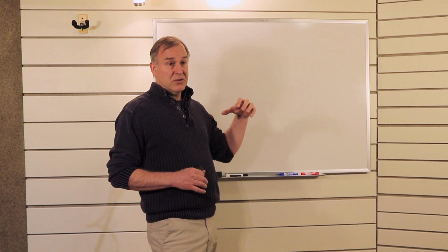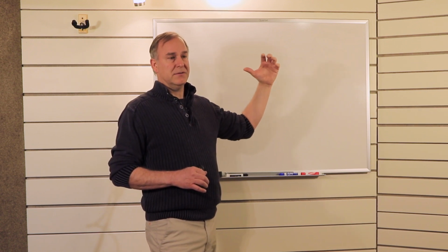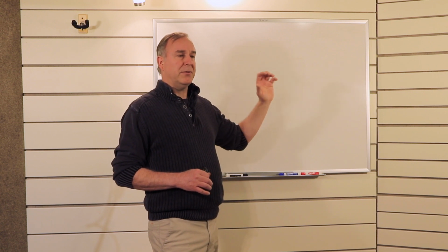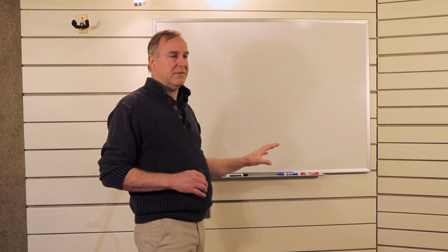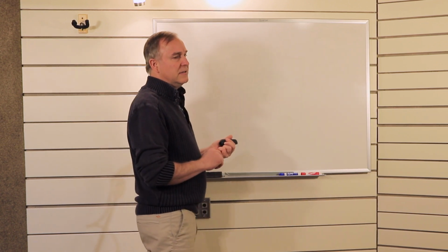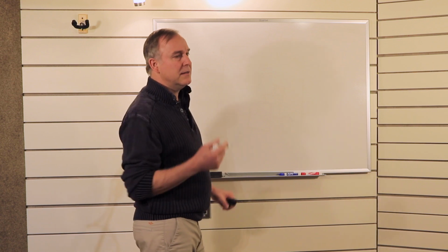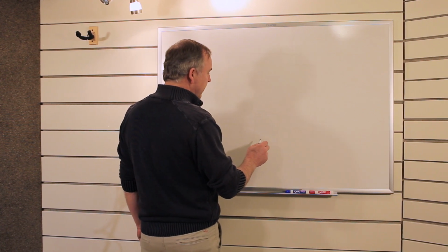Now, I'm not saying that you couldn't have a bladder or captive air style tank up in the system, but you will never have a plain steel tank that's stuffed back in the corner like you can do with a captive air style tank. There's an important installation detail that you need to pay attention to with these plain steel tanks that also is going to give you a clue that you're looking at that style of tank. So here's what that looks like.